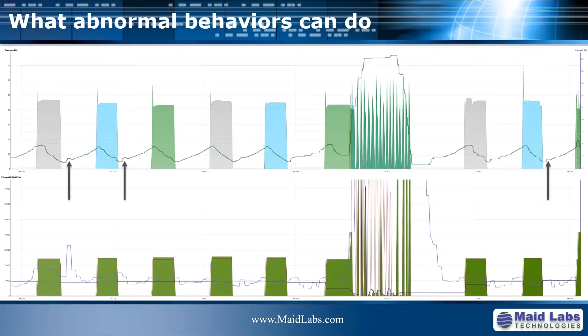Here you have a level going down without any pumps running. Usually it's very rare to have a siphon effect. I've analyzed thousands of stations in my life, and I've seen this twice, so most of the time it's a defective level sensor. It should be within the system to detect this kind of abnormal behavior, because if it starts doing it when it's not important, it will be catastrophic when it becomes important.